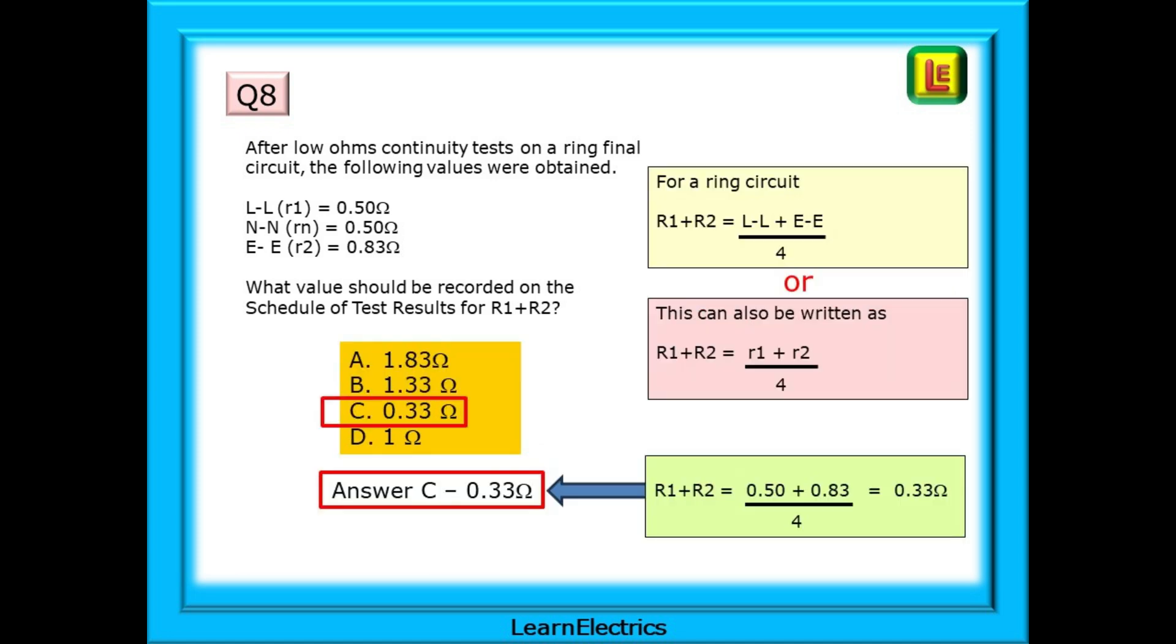Answer C should be your choice. Some books will show the formula as L to L and E to E divided by four. Others will show it as little R1 plus little R2 divided by four. So we have 0.5 plus 0.83 and then divided by four. This will give us the answer of 0.33 ohms.